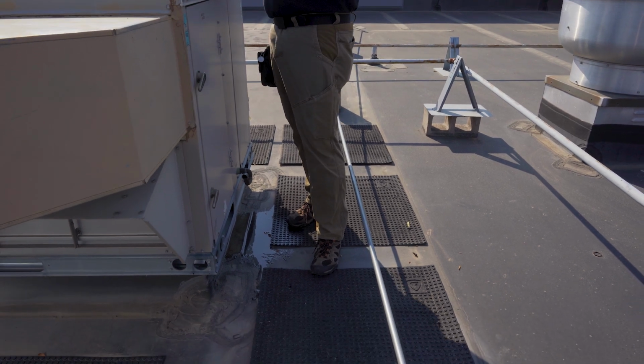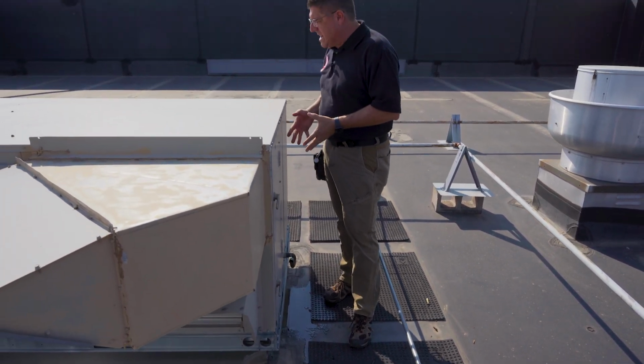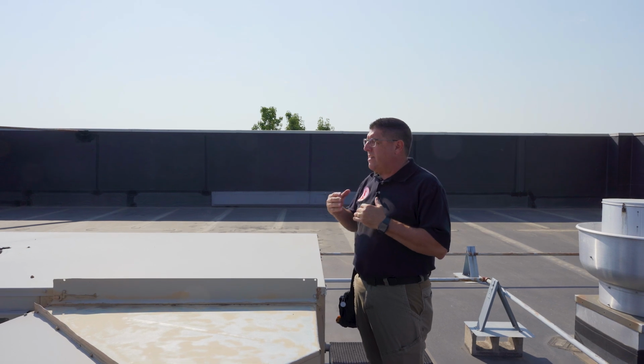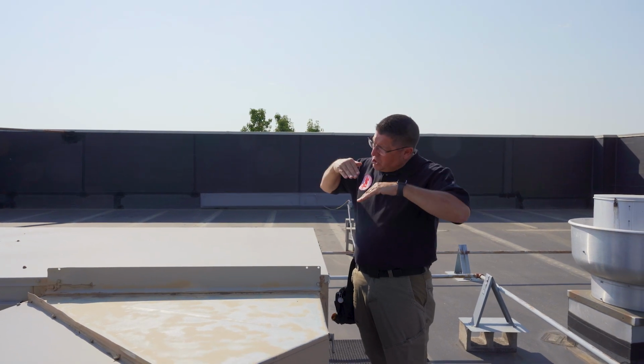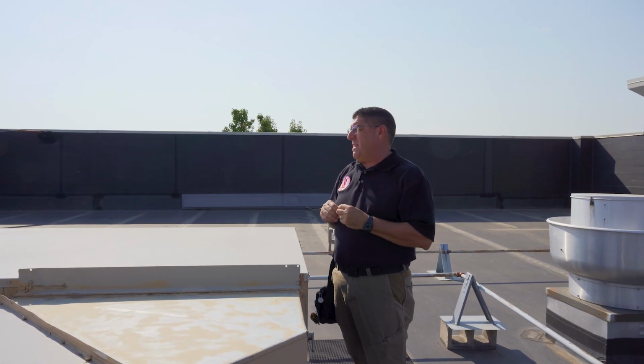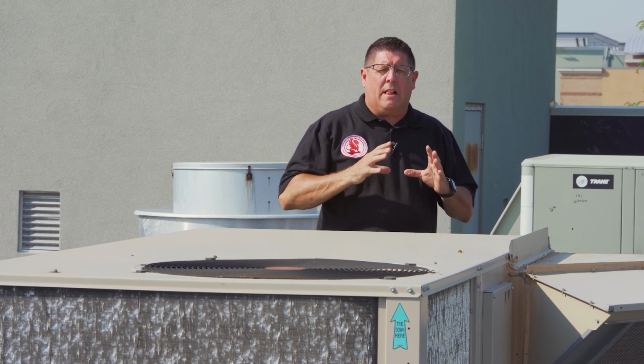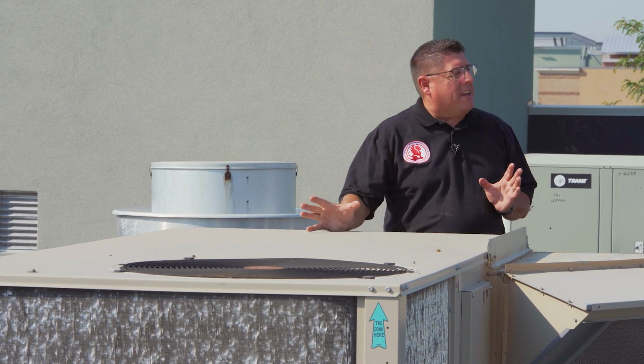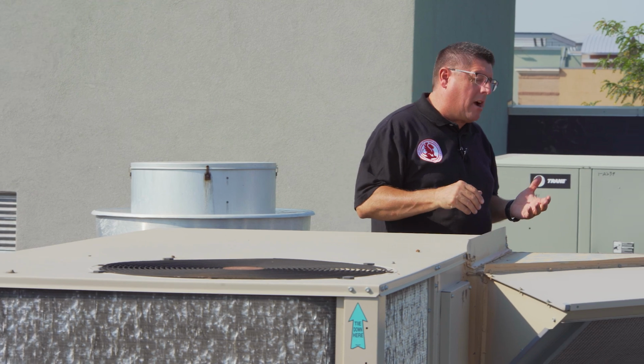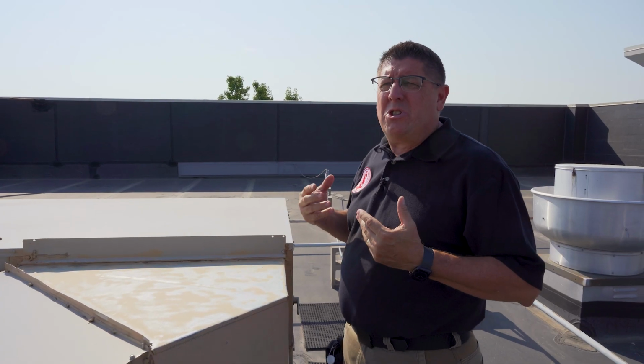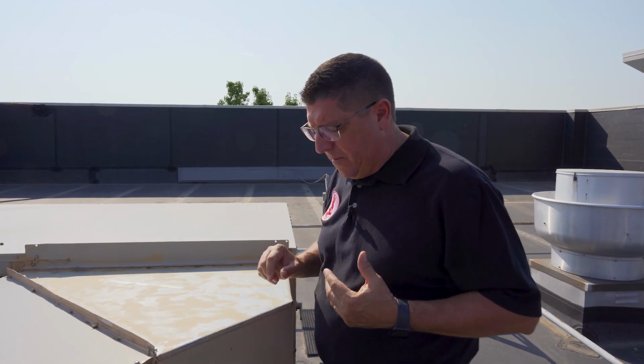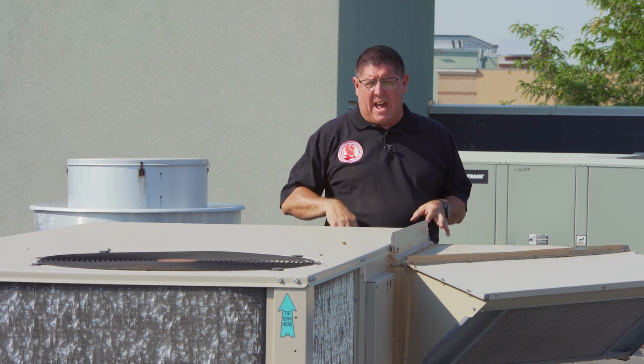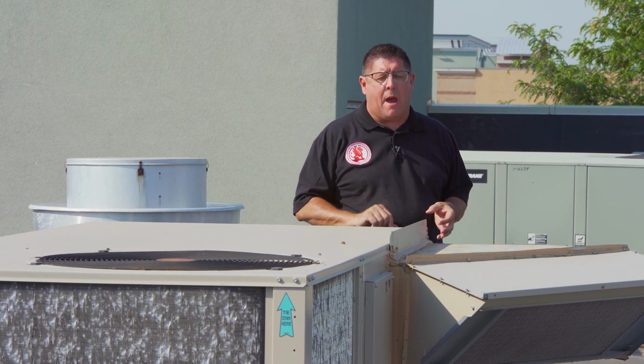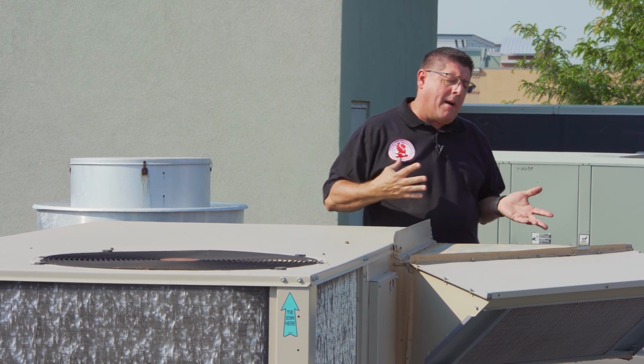Condensation pipes are absolutely critical to the maintenance of this piece of equipment and the safe operation, because that trap that's created by that condensation pipe does not allow fresh air directly into the ductwork. Fresh air into the ductwork can be a nuisance and dangerous to anybody that's on the inside of the building. So again, identifying the condensate drain and making sure it's properly trapped is very important. Then we can migrate around the unit.